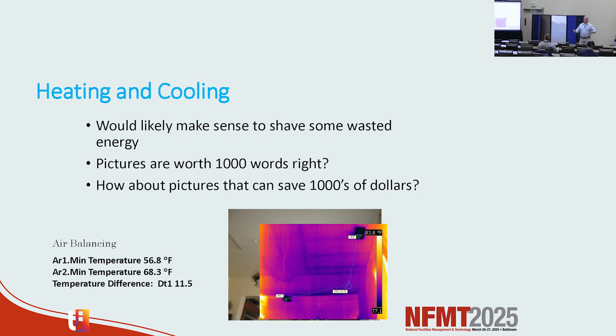If we focus on the hog of it, it's the HVAC. Saving some energy, a picture's worth 1,000 words. How many of you use the term air balancing? It's an effective tool. You ever get one office that says it's hot and one that says it's cold? Taking a thermal camera around that building can help determine that. Whether you have small 5-ton, 15 or 50-ton units on your roof, or a central plant, the thermography camera is that tool that can help you see if that equipment is working as it should.